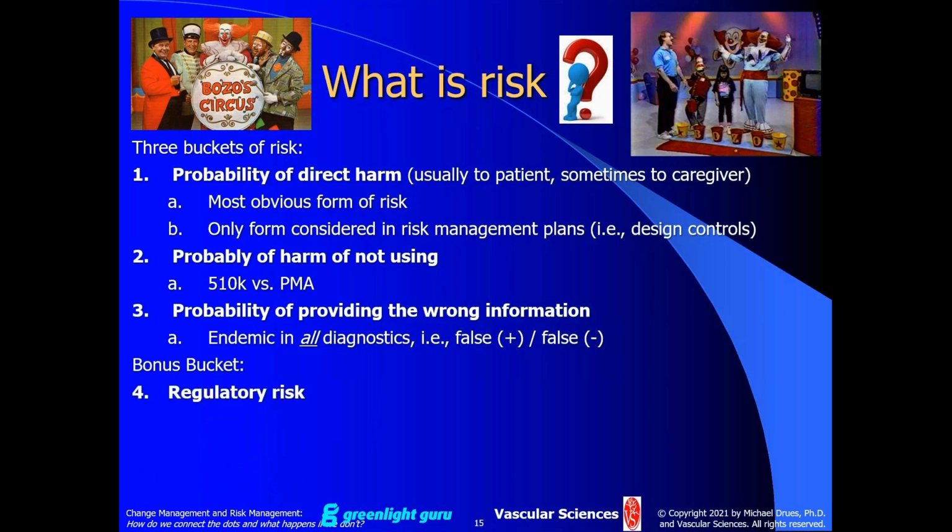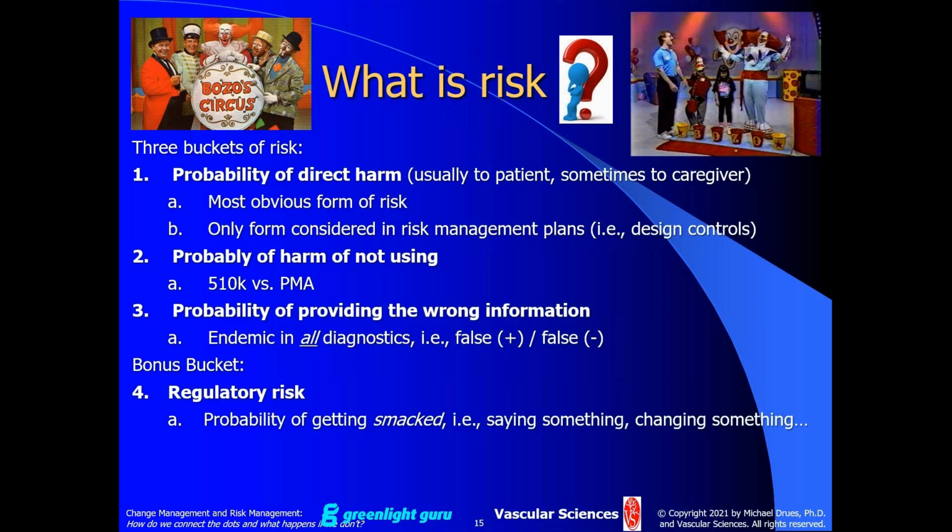In addition to that, there's my bonus bucket, what I call regulatory risk. Regulatory risk has a couple of different connotations. One connotation is the probability of getting smacked. In other words, what if you say something about your device, or in our case, we change something about our device, and FDA comes knocking on our door and says, hey, you've changed your device. We don't remember you ever coming and telling us about it and talking to us about it. What the heck is going on? That's one connotation of regulatory risk.